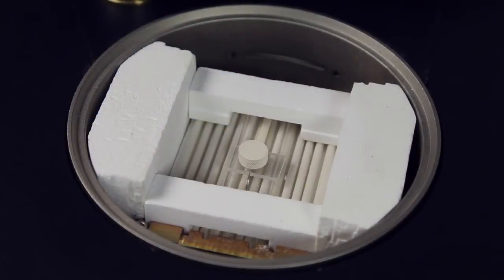Samples can be run under air, inert gas, or vacuum. Temperatures from minus 160 degrees C to 1400 degrees C are available using different furnace types. Temperature resolution of 0.1 degrees C is typical. The furnace is capable of heating up to 100 degrees per minute and cooling from 1400 degrees C to 50 degrees C in less than 10 minutes.